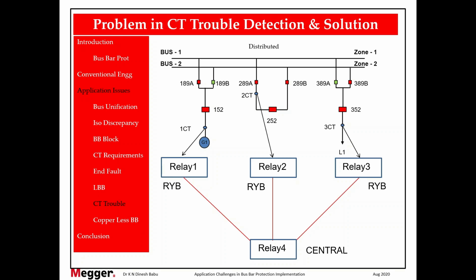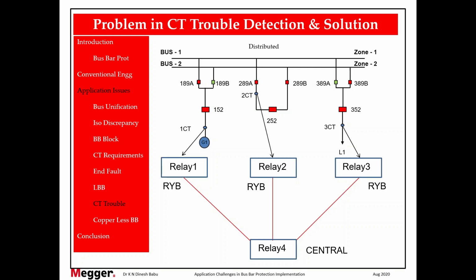The first input, zone 1 CT trouble, one alarm is available. Second input, a negative sequence current in one CT. If these two are satisfied, then CT trouble in bay 1. So the same logic can be repeated for every bay. So the operator is not only informed about CT trouble in which zone, but is also informed about CT trouble in which bay. Okay? So this is very easy in a distributed bus bar arrangement.